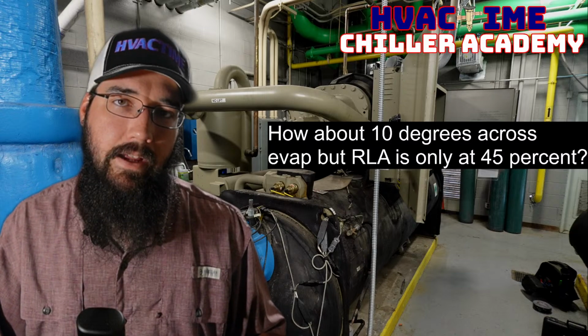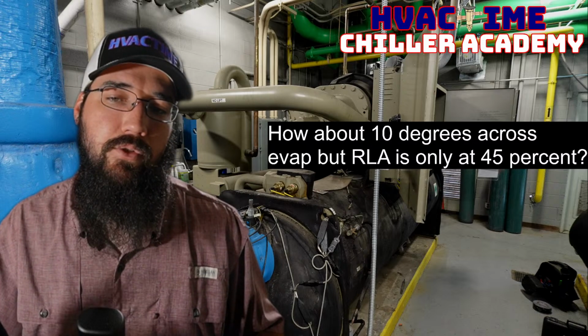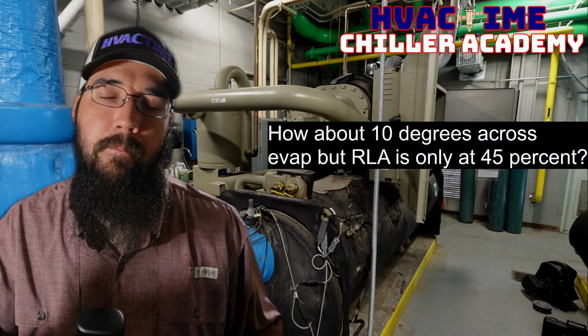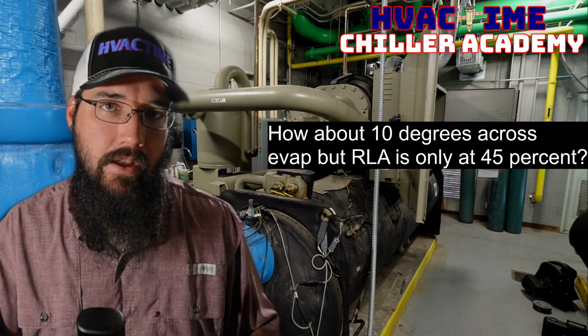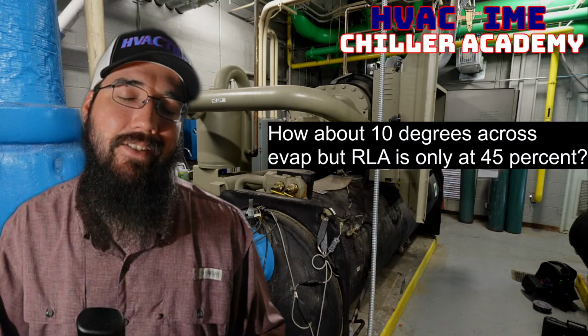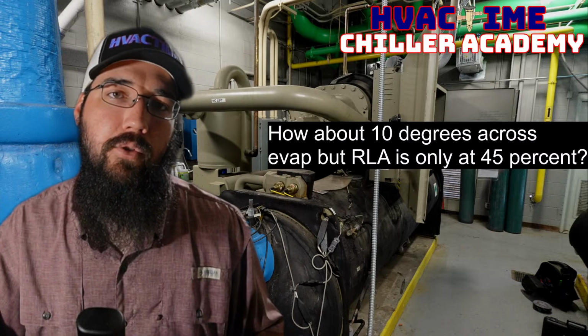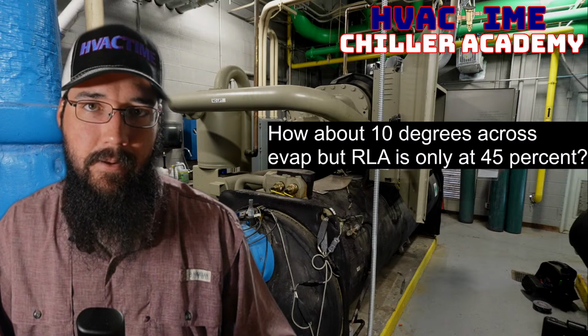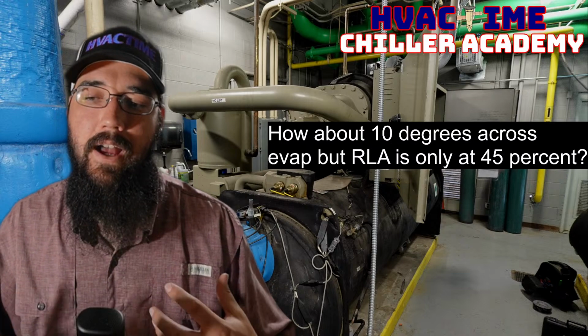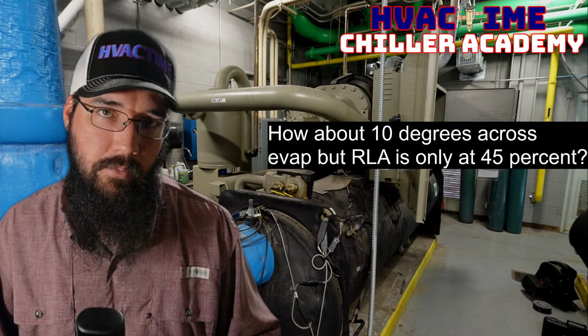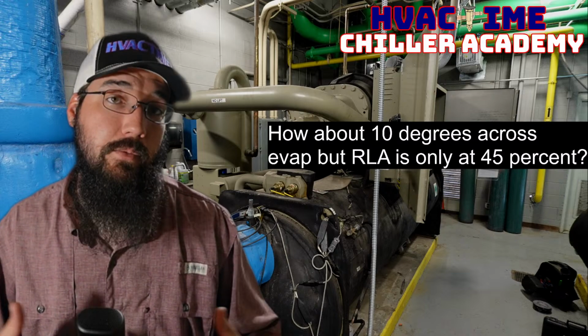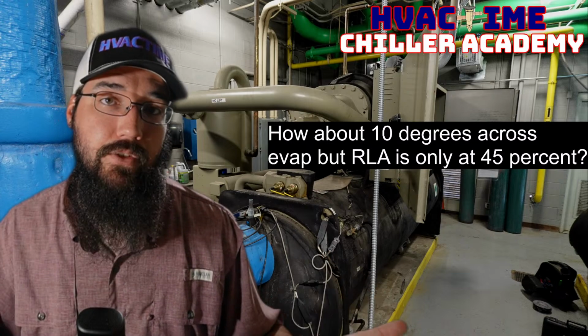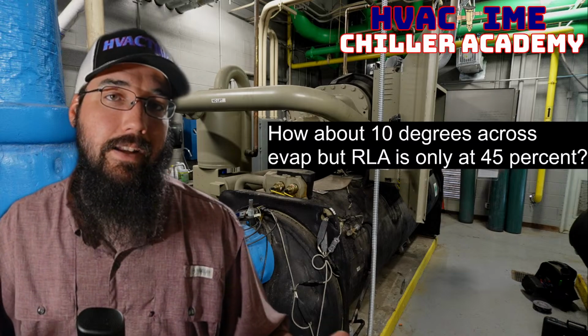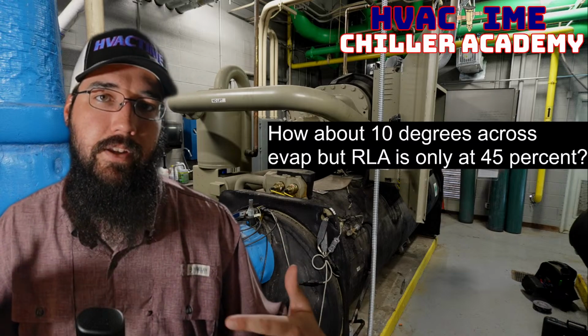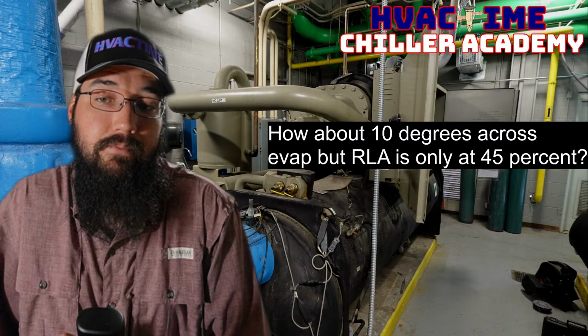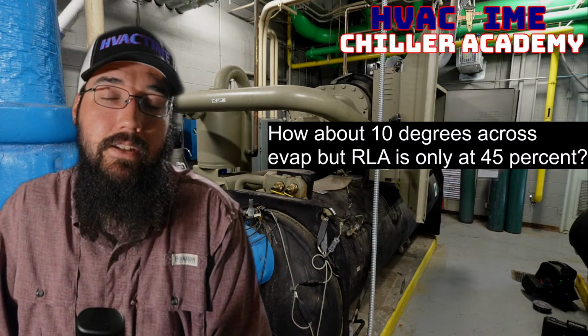So RLA is not a matter of, is this compressor running at the maximum load that it could possibly handle? It is how much work it is having to do to flow the volume it's being asked for at this time. That is how I would characterize what RLA is communicating. The compressor may be able to stage up more if it needed to, but if you're making set point, it doesn't need to. Because of our lift conditions, it may not require as much work to get it there.